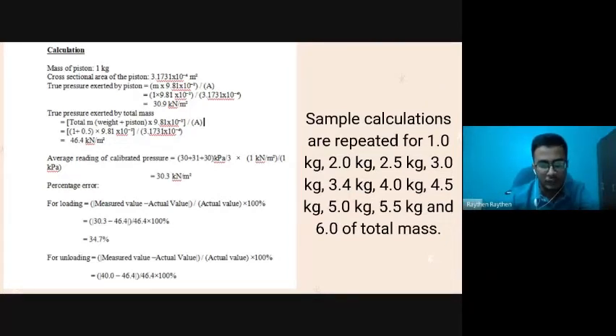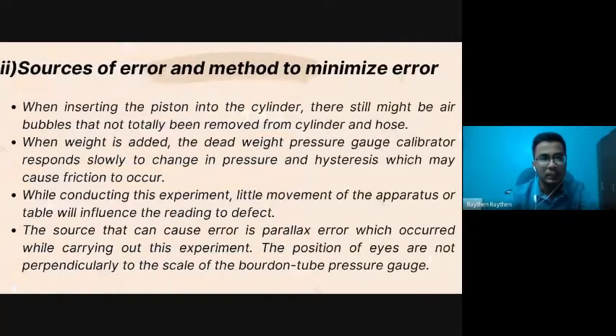For unloading, the same formula: modulus of measured value minus actual value over actual value times 100%, which we got 13%. So sample calculations are repeated for 1 kilogram, 2 kilogram, 2.5 kilogram until 6.0 kilogram of total mass. Next will be the sources of error and method to minimize error.